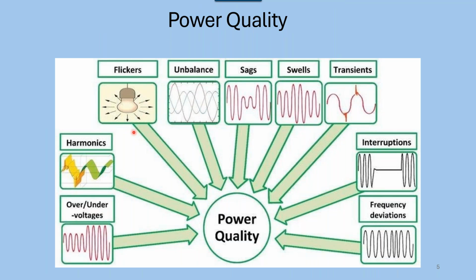Flicker, we've all seen our lights flicker. It's actually an interesting phenomenon. What I found out causes flicker a lot of times is electronic devices, especially 3-phase devices. They actually have 2 of the phases shorted out at the same time, and that causes the flicker to occur. I've got a white paper just on that if you want more information.